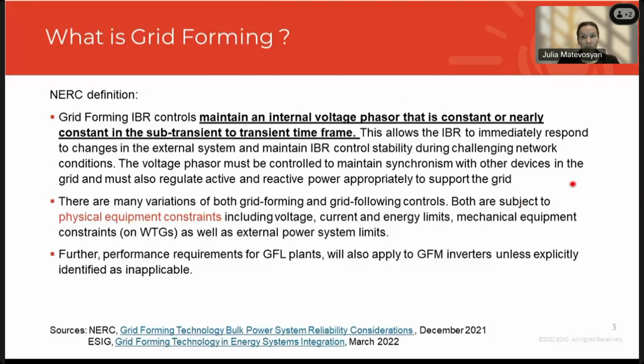So as we talk about advanced functionalities from inverter-based resources, we run into this broad term that we call grid forming. And so grid forming controls, I pulled this definition from a NERC white paper from 2021, and broadly grid forming controls are defined as controls that maintain internal voltage phasor constant or nearly constant in subtransient to transient time frame, and that allows the inverter-based resource to immediately respond to changes in the external system and maintain control stability during challenging network conditions. The voltage phasor must be controlled to maintain synchronism with other devices in the grid, and must regulate active and reactive power appropriately to support the grid.